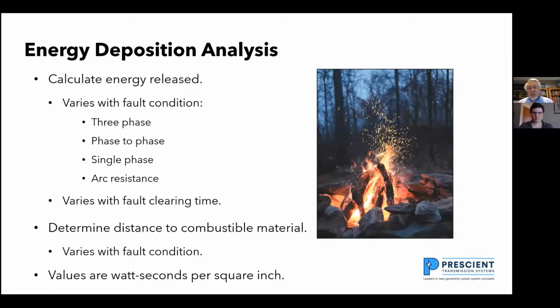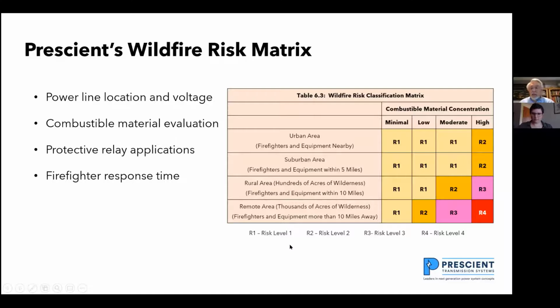The values that we're calculating are watt seconds per square inch. The risk matrix we use looks at power line location and voltage, combustible materials, protective relay applications, and firefighter response time. If I look at the graph here, table 6.3, the concentration is when I have a large concentration of combustible materials. If it's an urban area, firefighters and nearby equipment can get to the fire. It's not a big deal.